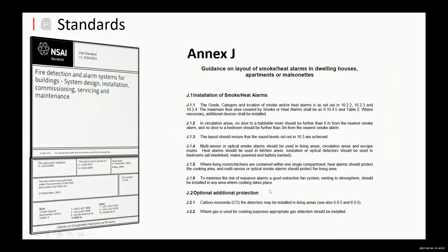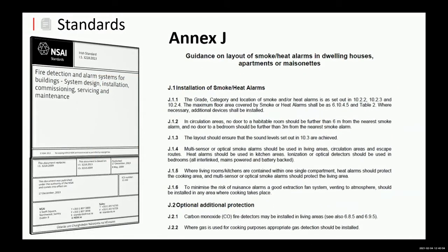Again, Annex J would just give you, I suppose, a summary of what we're after talking about there. There is one part of it here. The living room and kitchen are contained in one single apartment. A heat alarm should protect the cooking area, and a multi-sensor or optical sensor should protect the living area. Now, that's a bone of contention out there at the minute. We see it a lot ourselves. We get a lot of calls about this. So our advice on that is a heat detector covers the kitchen area, and either a multi-sensor or an optical unit would cover the dining room or the living area. Depends on what they're calling it.